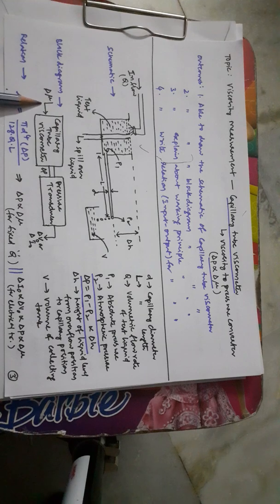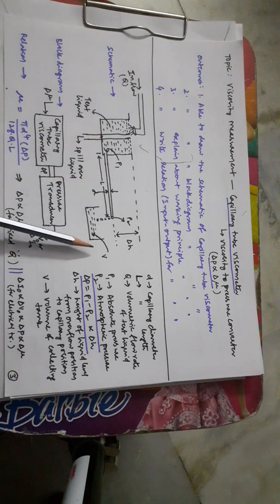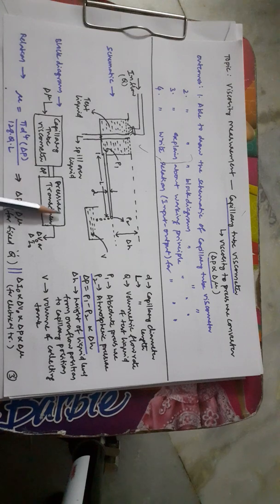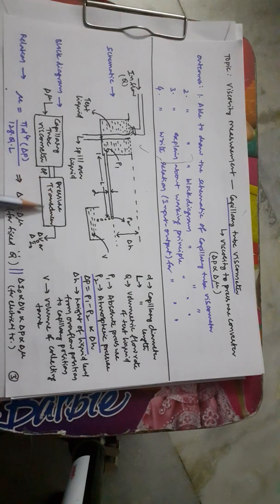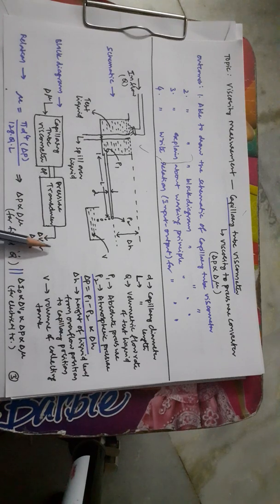The capillary tube acts as a mechanical transducer — input is delta mu and output is delta P. To obtain an electrical output, this mechanical setup is connected to an electrical transducer. In the block diagram, the capillary tube viscometer is the primary transducer with delta mu as input and delta P as output. A second pressure transducer measures the differential pressure and produces an output voltage, which can then be converted to current using a V-to-I converter in the required range.